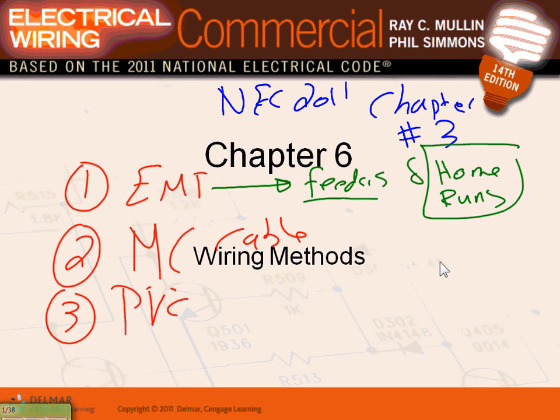Now, can I use an EMT conduit for everything else? Yep, you can, for the lights and everything else. It's better, it allows you future expansion, many conductors and so forth. Cables, for the most part, are for branch circuits. You're going to be using them for branch circuits. That's probably where you would use MC cable, branch circuits. Though you can use it for feeders, in a commercial building, the best application for it is a branch circuit.